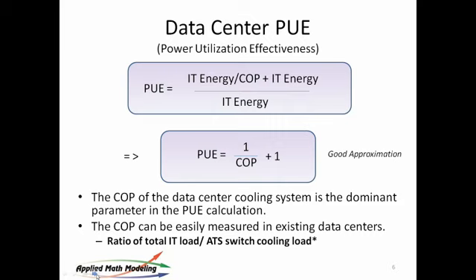It ends up that COP, because if you look at the dominant parameters in the PUE metric, you find that COP is the dominant one, and that therefore PUE is really the inverse of COP plus 1. The way to think about this is that a good COP would be about 4, which means that it only takes 1 kilowatt to reject 4 kilowatts. It only takes 1 kilowatt of electricity to pump 4 kilowatts of heat out of the room. That would be a good COP. And therefore, 1/4 plus 1 is 1.25, and that's a good PUE. So it's a fairly easy way to calculate PUE and to think about it.